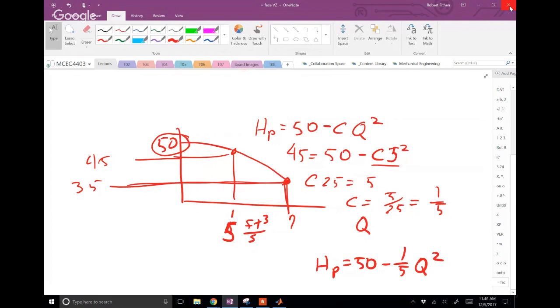And then here you basically said that HP is 45. Yeah, so what I was doing, I was picking a spot right on the curve, and if it comes over and say, well, that's 45. So the head of operating there is 45. And this is directly brought down because it's the intercept. And then this is the 5. So this is the flow rate here. So I'm pulling it off. That's a 5. Okay. Yeah.